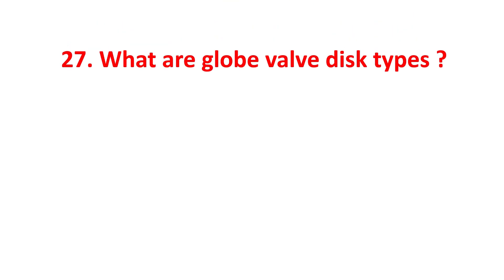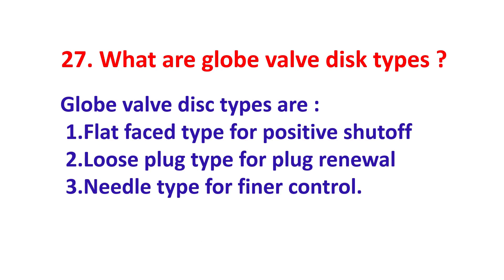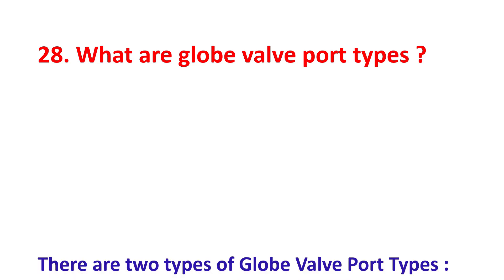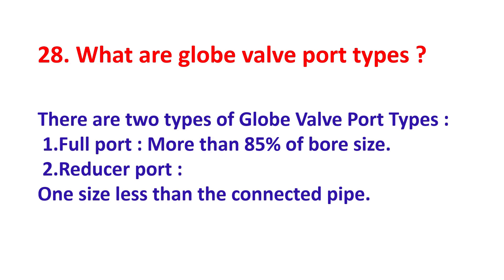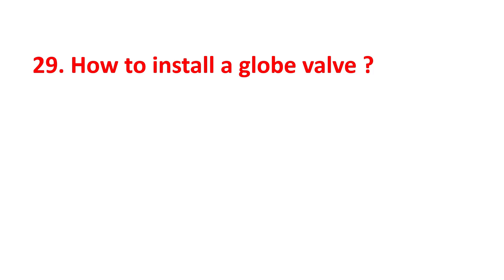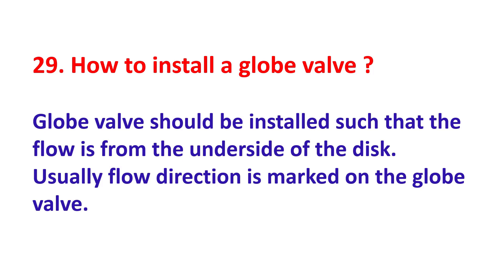What are globe valve disc types? Globe valve disc types are: flat-faced type for positive shut-off, loose plug type for plug renewal, and needle type for finer control. What are globe valve port types? There are two types: full port, more than 85% of bore size, and reduced port, one size less than the connected pipe. Globe valves should be installed such that flow is from the underside of the disc. Usually, the flow direction is marked on the globe valve.